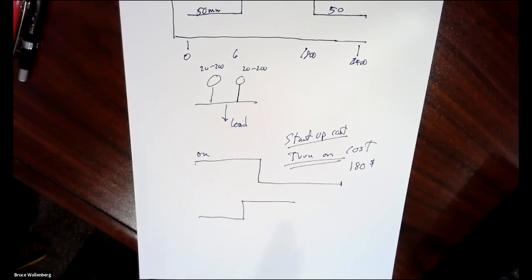Well, that whole period might take 6 or 8 hours to start the boiler up, that's running fuel into it. It starts to heat up, water starts to boil. Eventually you create steam and the steam is going into the turbine and it gets up to enough pressure and the turbine starts to turn and eventually comes up to synchronous speed. That is controlled over a long period of time and you're burning a lot of fuel, but you're not creating any electrical energy. All you're doing is getting everything up to temperature and you're getting the turbine generator turning at, let's say 1800 RPM synchronous speed on a 60 Hertz system.